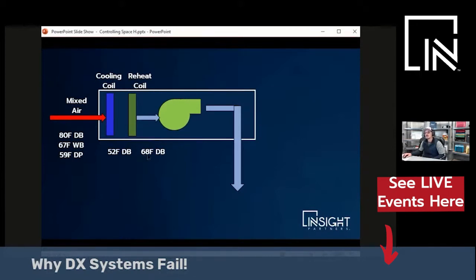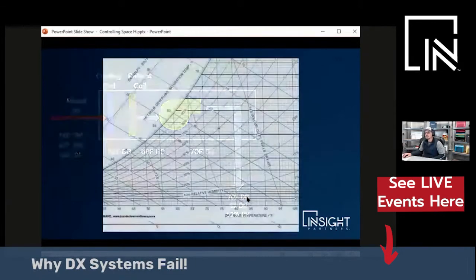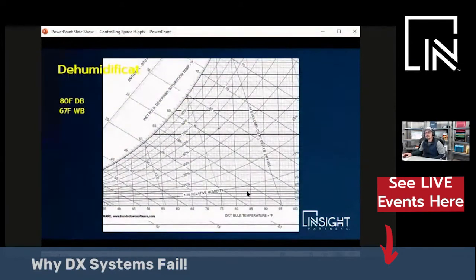We reheat it with the heating coil, let's say to 68. These are arbitrary example numbers. You pick up a few degrees with the fan. You blow this 70-degree air into the space, which is relatively warm. And everybody's good to go. So now you're dehumidifying the air and not freezing everybody out.